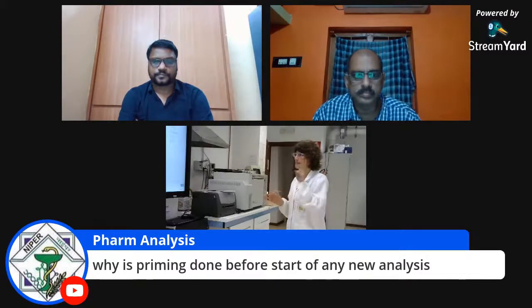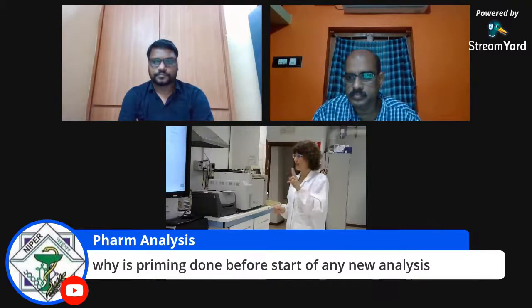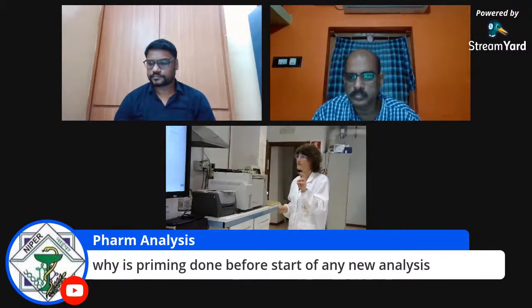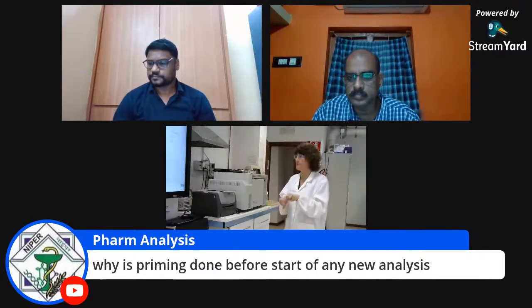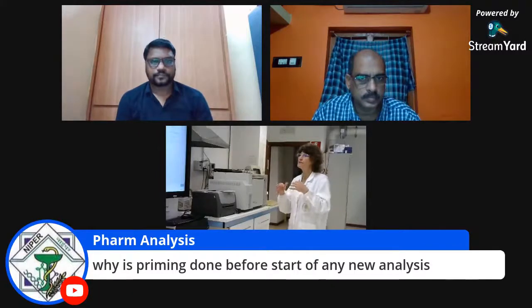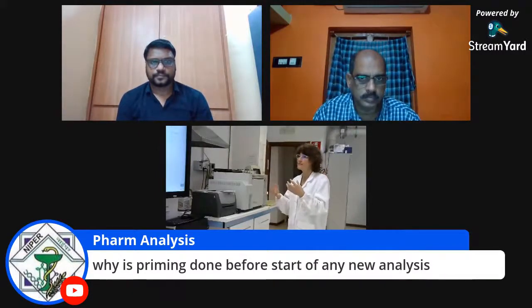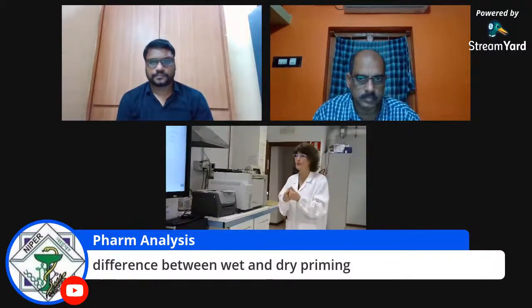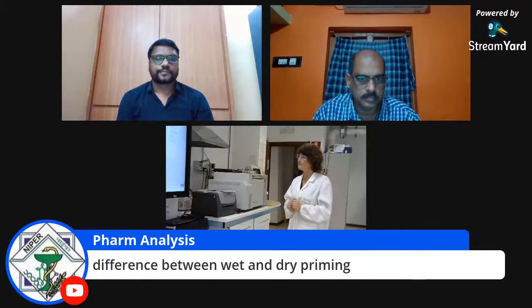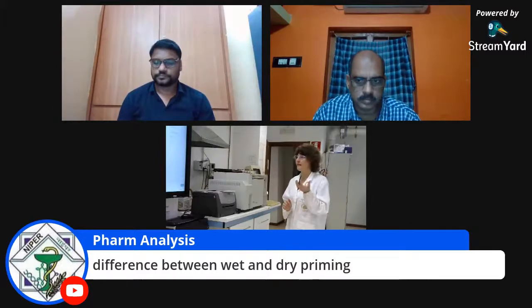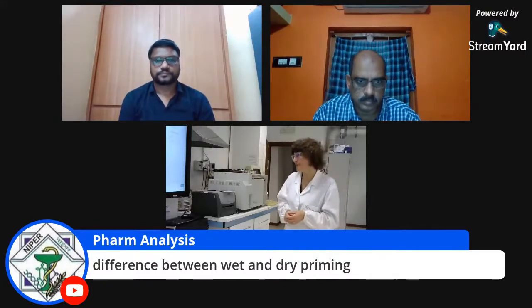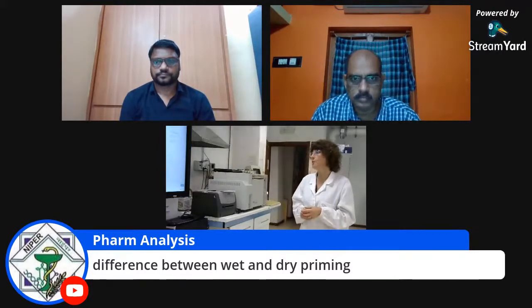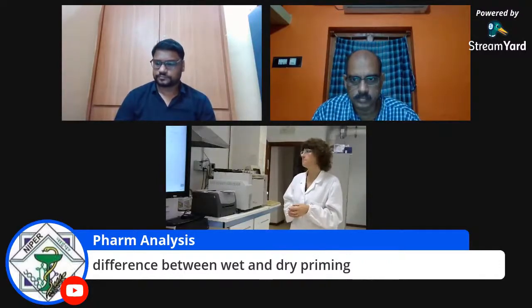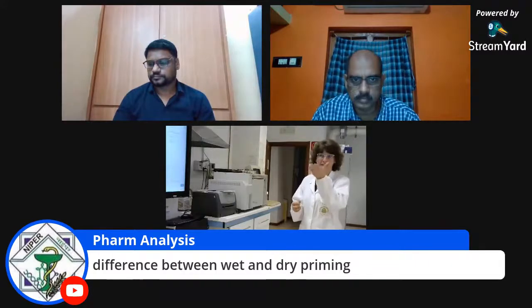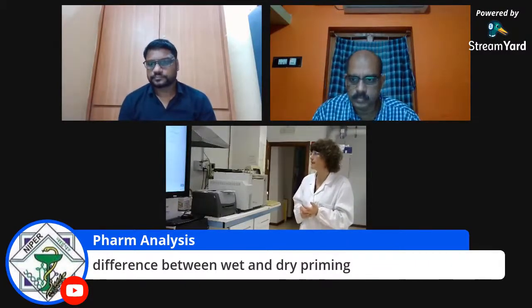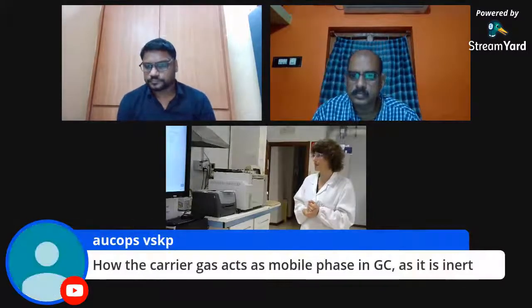So you prime the system in two cases. When you change the eluents, and you have to be very attentive because you do not want to provoke precipitation of buffer ions. And when you start any new analysis, just to eliminate very, very big bubbles that are not able to be eliminated by the degasser. The degasser, remember, is only useful to eliminate dissolved gases. Difference between wet and dry priming. Actually, we only use wet priming. I'm not familiar with dry priming, and in this chromatography, you only use wet priming for sure.